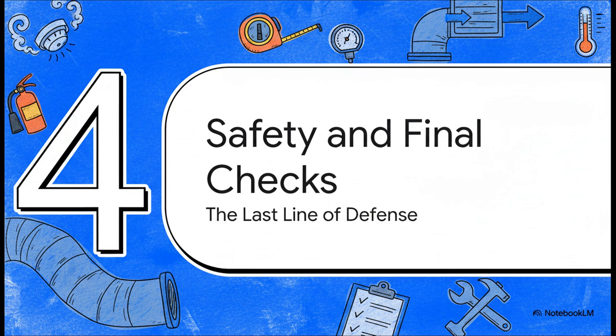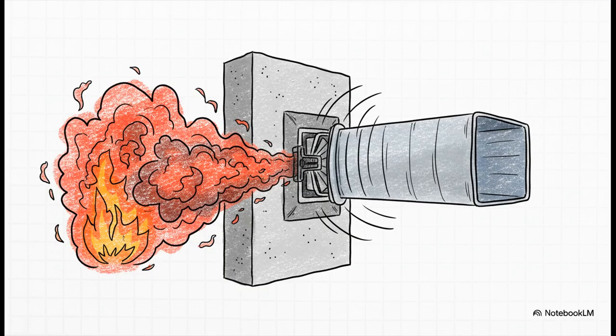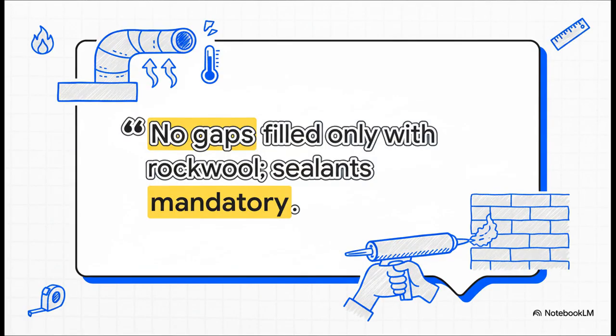Which brings us to the final and, without a doubt, the most critical part of this whole process. This is where everything, the standards, the measurements, the quality control, it all comes together for the last line of defense: safety. Because look, being comfortable is nice, we all love it, but the absolute number one non-negotiable job of an HVAC system is to keep people safe, especially in a fire. The last thing you want is for the ductwork to become a superhighway for smoke and flames. This quote is pulled straight from an installation manual, and it's not a suggestion, it's a command. It means every single little hole where a duct passes through a wall has to be sealed up tight with a special fire-rated sealant. No gaps, no excuses, the stakes are just too high.